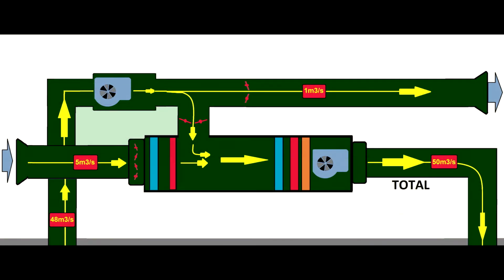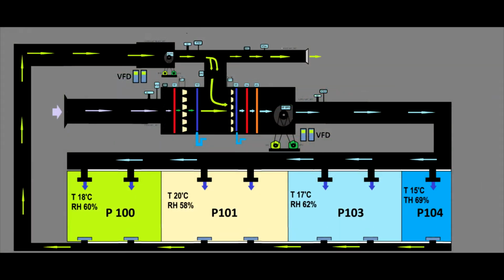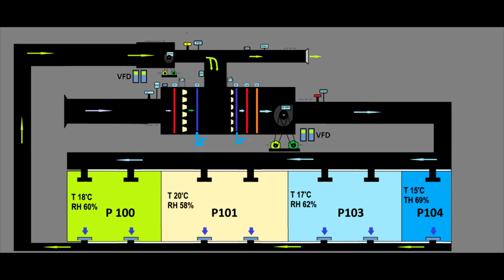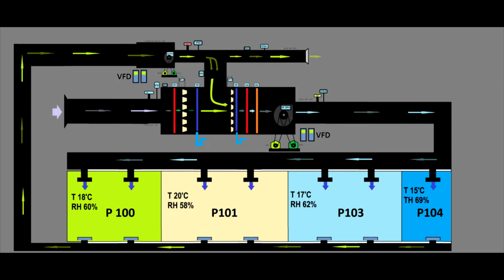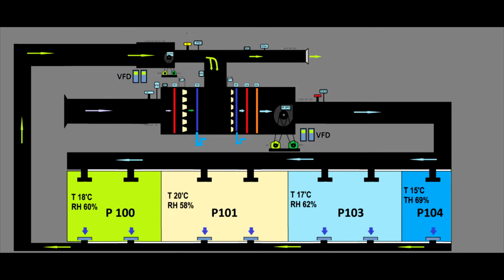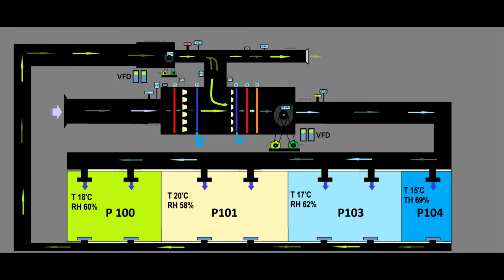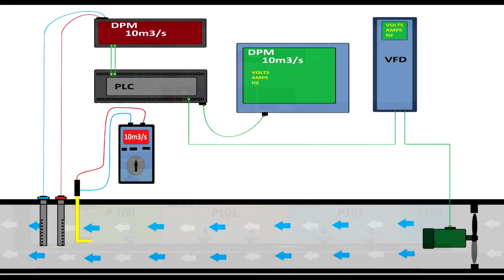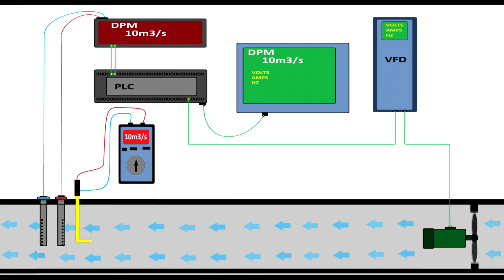And once you have motors and dampers, you'll be able to control the airflow, the air quantity, and the air direction. And what you'll see here is how the air circulates through the air handling unit and how the air reaches the rooms. Also, you'll see how the air will return to the extractor fan. Part of the air will be exhausted and part of the air will be recirculated. And here you will observe that there's a programmable logic controller that controls the fan through the variable speed driver.